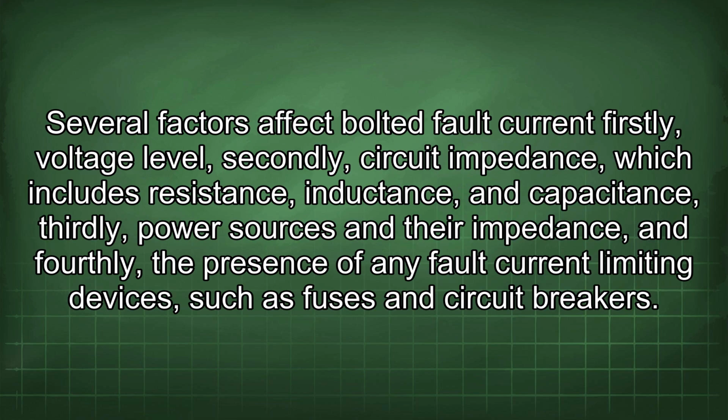Several factors affect bolted fault current. Firstly, voltage level. Secondly, circuit impedance, which includes resistance, inductance, and capacitance. Thirdly, power sources and their impedance. And fourthly, the presence of any fault current limiting devices, such as fuses and circuit breakers.